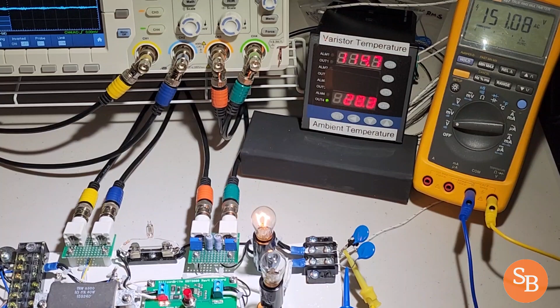And there goes - what happened there is there's a 1 amp fuse in series with the varistors, and the 1 amp fuse blew. There's a neon lamp across the fuse, so the neon has illuminated to indicate the fuse has blown. The varistors, look, they're at 161 degrees C. They're getting cooler now, cooling down. But they were hot enough that smoke was coming out. It was protected by this 1 amp fuse.